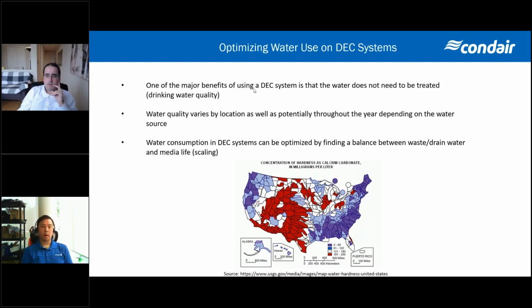But as we know, water quality can also vary by location, as well as potentially throughout the year, depending on where the municipality is pulling water at that time. So it is fairly tricky to optimize based on a specific water quality, as that could potentially change. But if we have an idea of what that water quality is at different times of the year, we can run different calculations to try and optimize that. But really, what we're looking at here is finding a balance between the water that we're draining out of the system and media life, effectively, or scaling on that media.